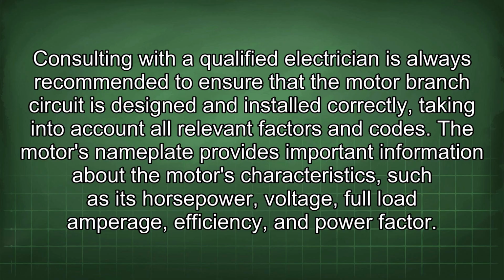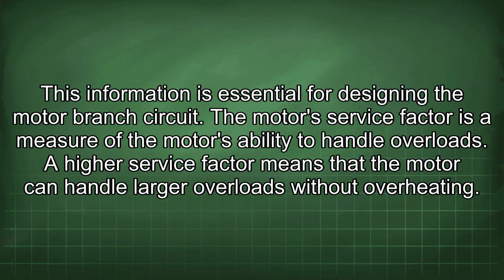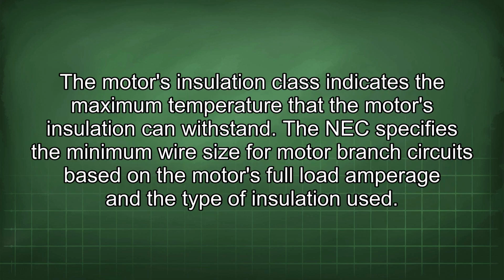The motor's nameplate provides important information about the motor's characteristics, such as its horsepower, voltage, full load amperage, efficiency, and power factor. This information is essential for designing the motor branch circuit. The motor's service factor is a measure of the motor's ability to handle overloads. A higher service factor means that the motor can handle larger overloads without overheating. The motor's insulation class indicates the maximum temperature that the motor's insulation can withstand.